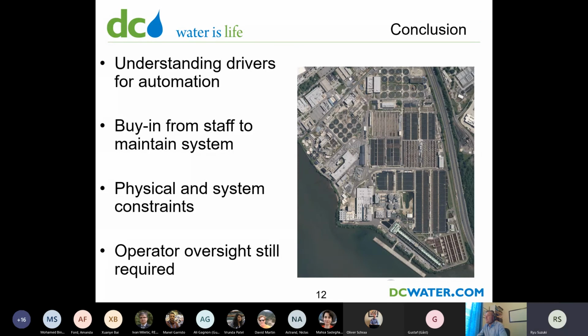Yeah, that is a great question. So maybe I'll answer the second part. In general, the MPC would only really work when the ammonia probe is fully calibrated. That's one of the main assumptions, and it wouldn't help us much if the ISE does drift and we lose calibration. So it's not a matter of having to retune the MPC. It's just making sure that you're able to stay on top of the ISE probe. Another thing we haven't really looked into is that I imagine the MPC would need to be retuned based on different seasons or mixed liquor concentration, various factors. But to be honest, we haven't fully looked into it yet to quantify the performance of the MPC in various conditions.